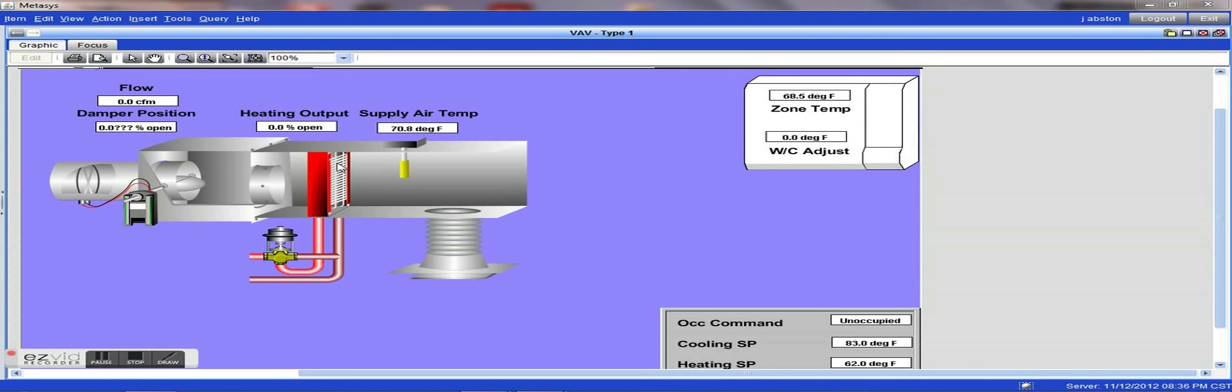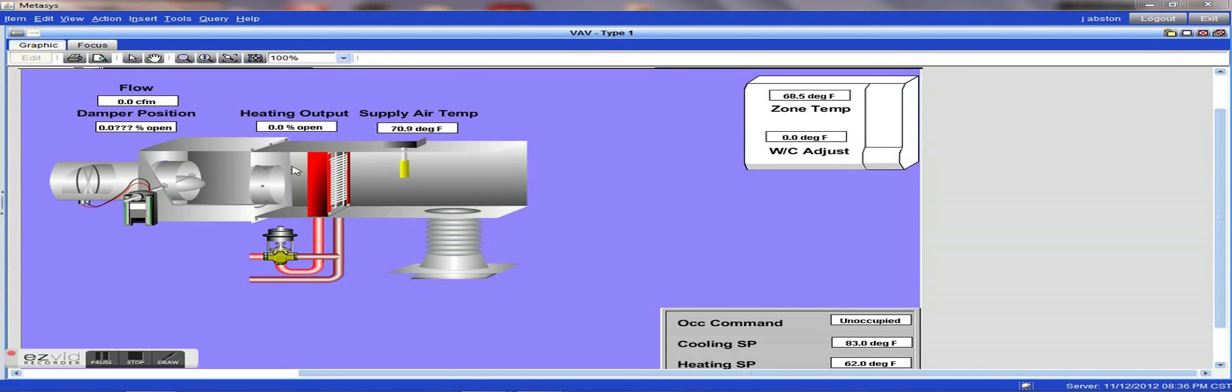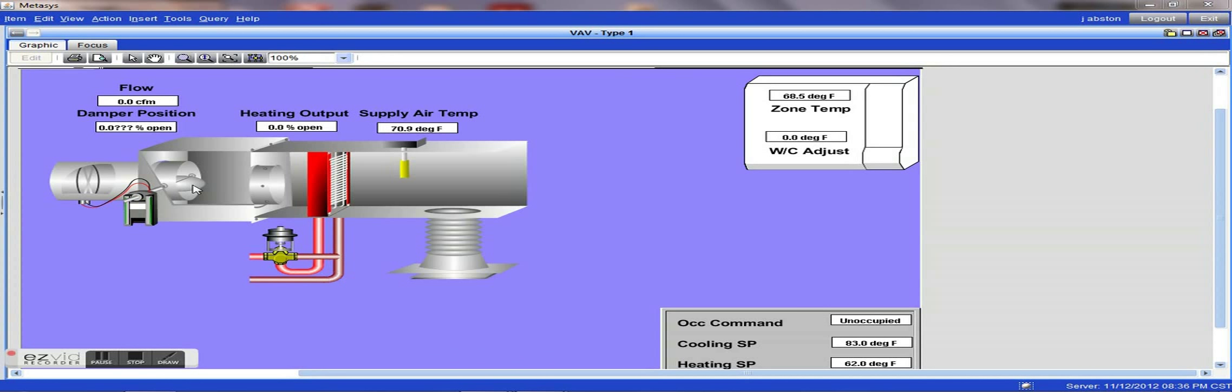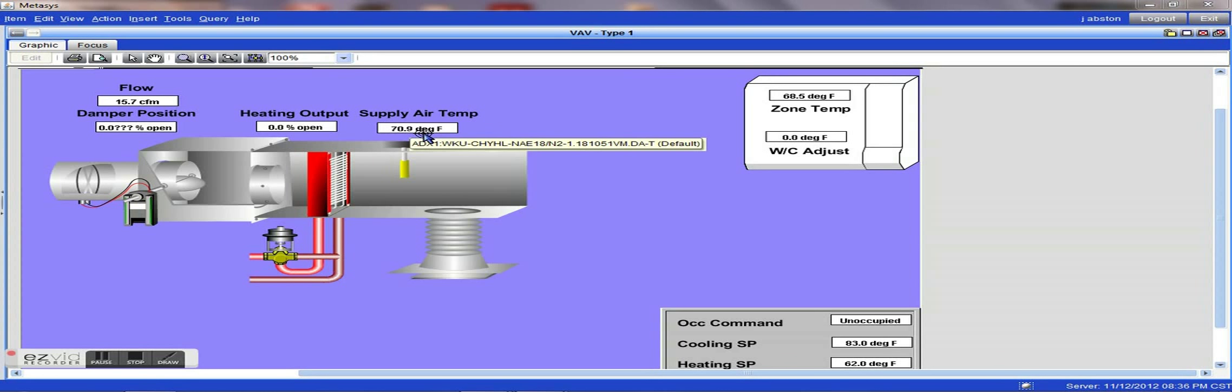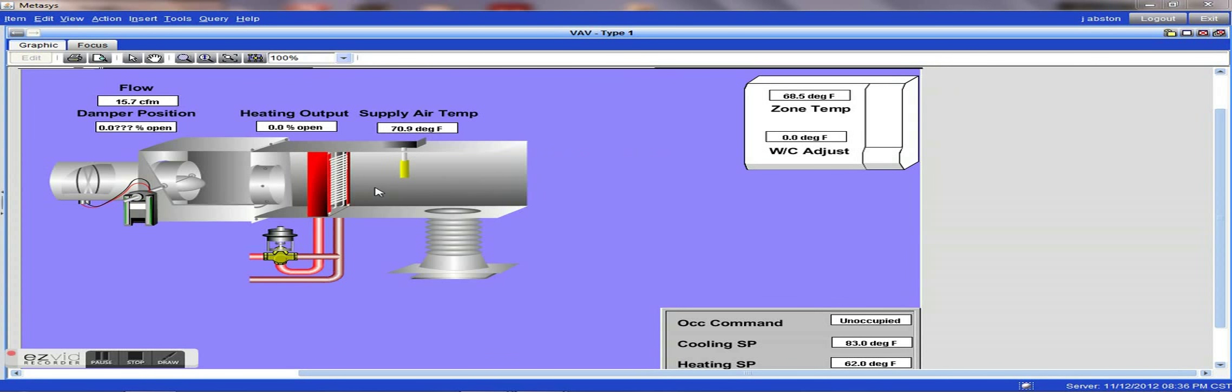If the coil is not adequately sized for the space, one thing that can happen is that you will lose effective heating. If you open the air flow up to a very high level, which is generally not done if everything is engineered and sized correctly for the space, you can actually drop the discharge temperature to where you lose your effective heating.